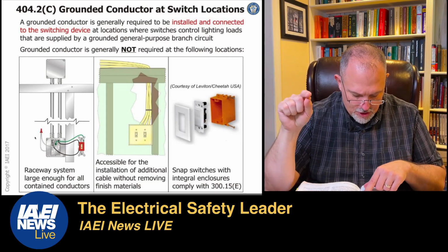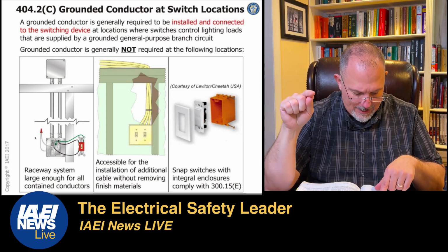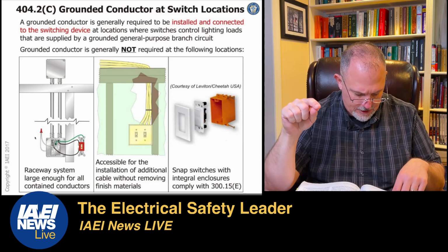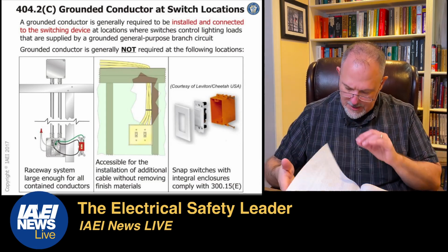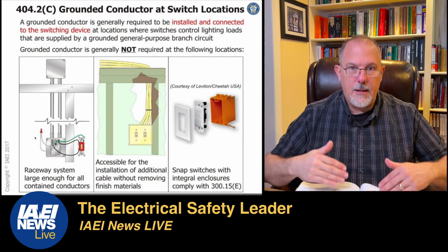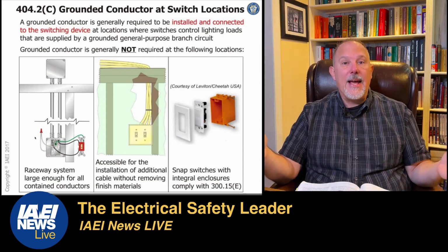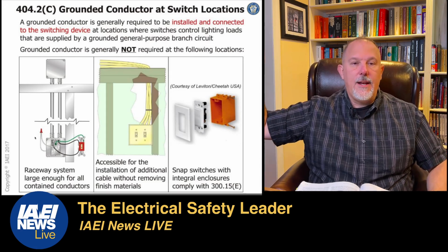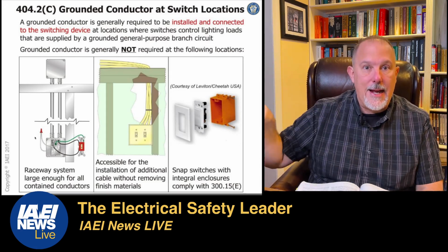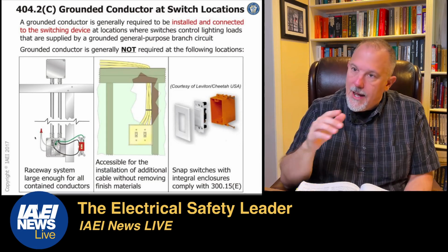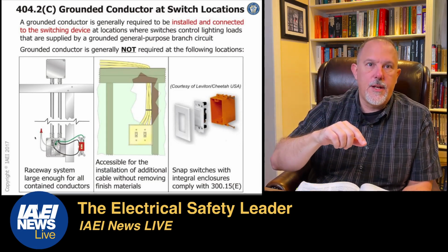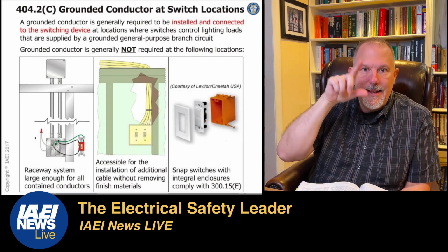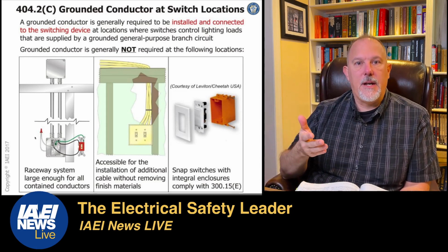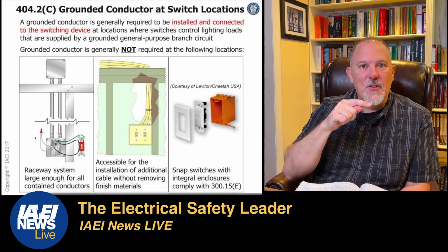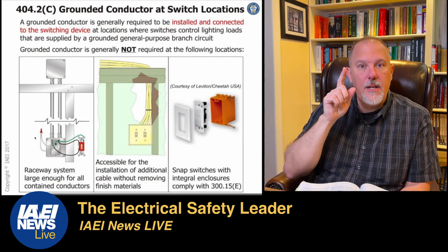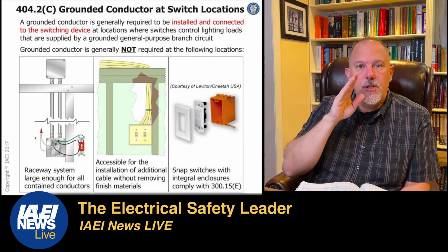A grounded conductor shall not be required to be installed at lighting switch locations under any of the following conditions, and then they have those 5 conditions. They deleted one, which I think they moved up to the parent text that says if you're controlling it at one location, then you've got to have that neutral at that one location. So I might have one location where I'm controlling an entire floor at a light switch from an occupancy sensor perspective. I'm going to need a neutral there. Okay, and you're going to need to figure that out ahead of time. So this changed.